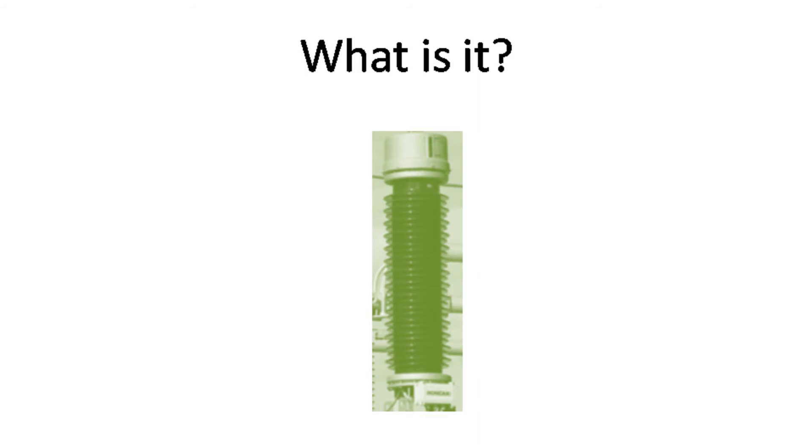However, the inductive voltage transformer, without the effects of a capacitive voltage divider, is much more accurate. But, on the other hand, it is bigger and actually more expensive. In fact, inductive voltage transformers are the default go-to voltage transformers up to 130 kV, and most of the time, these are just referred to as voltage transformer.